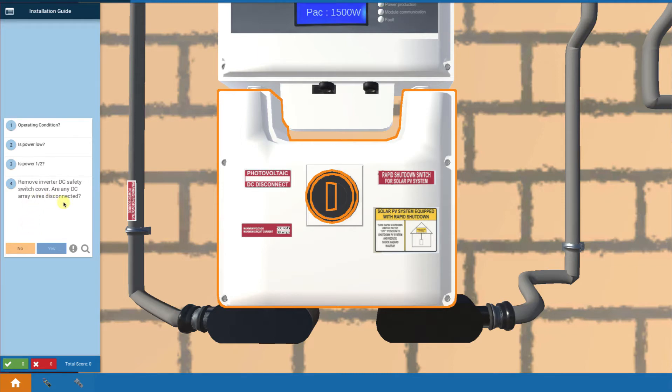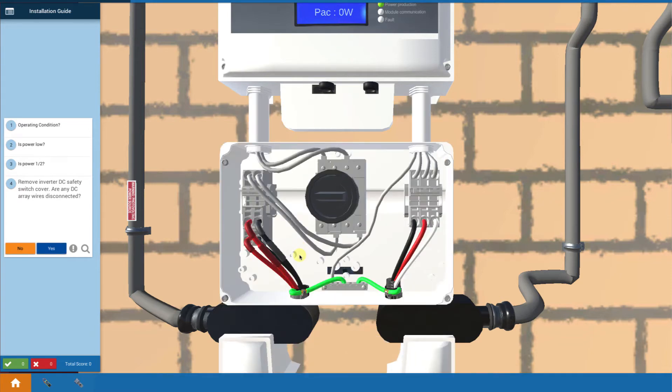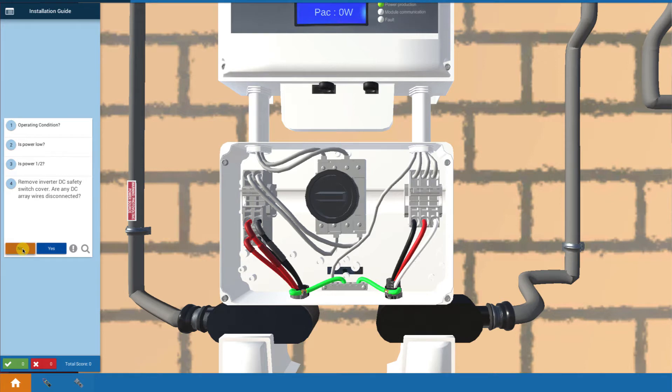Let's take a look and see if any wires are damaged in the DC disconnect. I'm going to touch the knob to turn it off. Notice that the power goes to zero. I touch the cover and take a look. The wires inside are not damaged or loose, so that's not a problem.